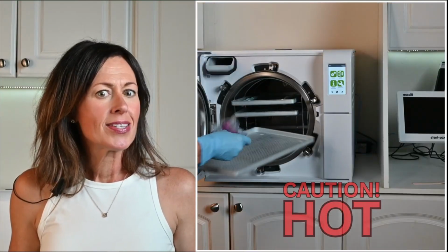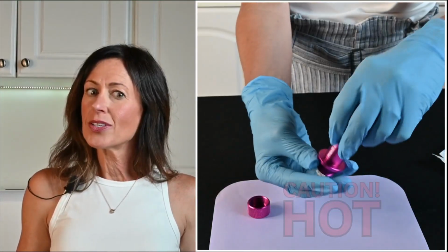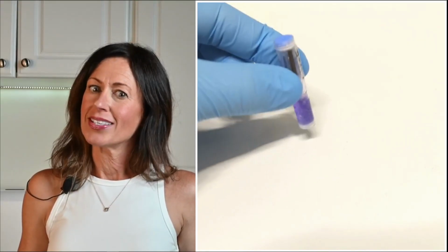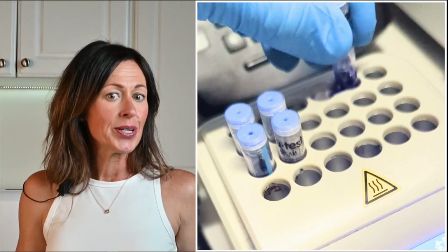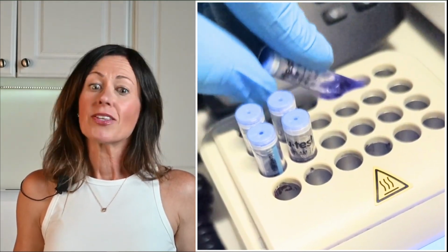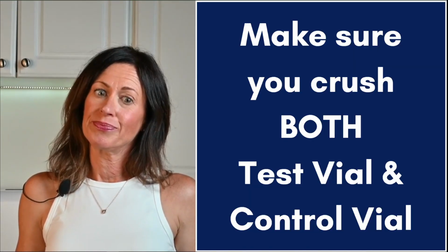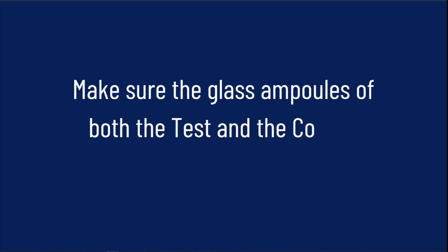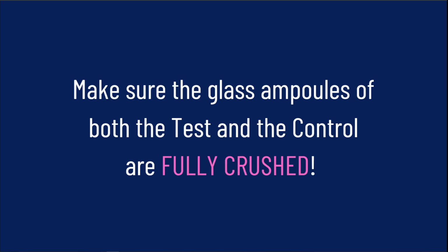After your sterilization cycle is complete and the test vial has cooled, gently tap the vial to settle the liquid, then place it into the built-in crusher of the incubator. Take the control vial and crush it as well. Make sure the glass ampules of both the test and the control are fully crushed, so the spore strip is in contact with the growth medium.